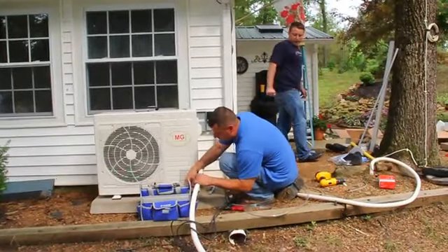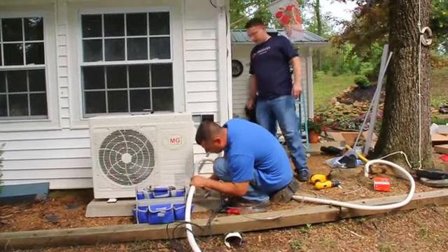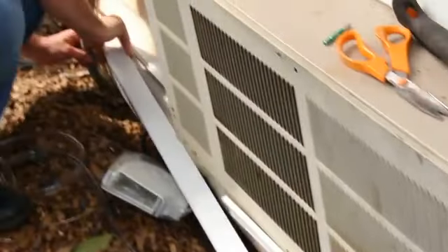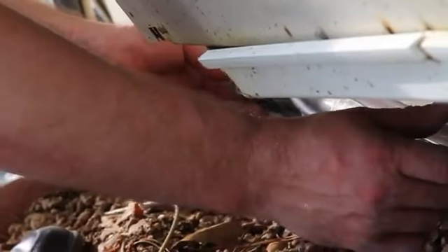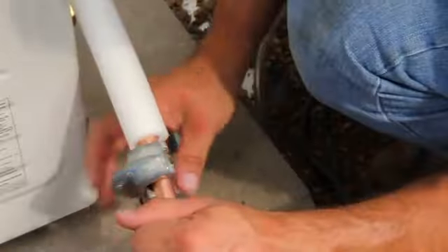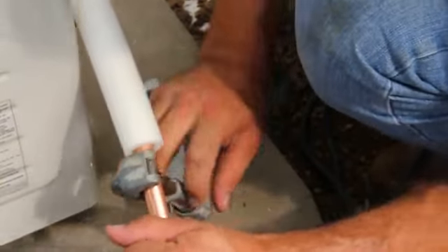If the condenser is mounted higher than the air handler, you must ensure that there will be proper oil returned to the compressor. You will need an inverted trap immediately exiting the condenser unit and additional oil traps for every 16 feet of vertical pipe run. With those requirements met, you are ready to cut.